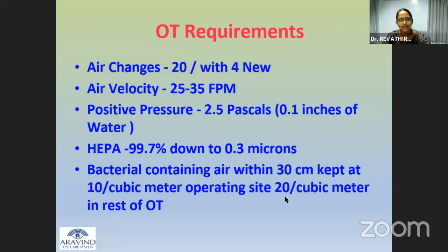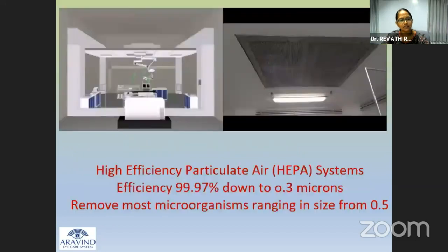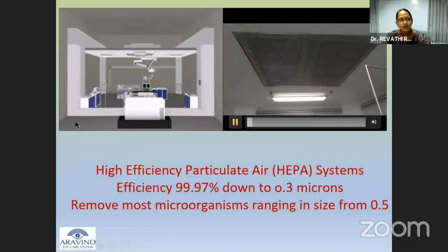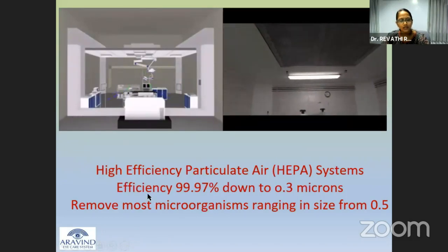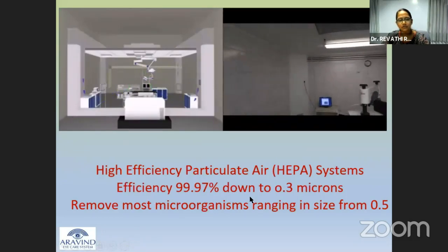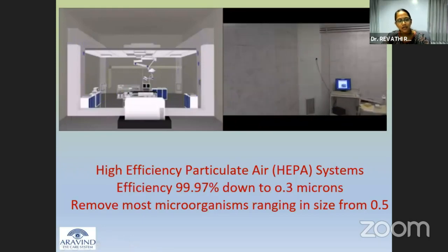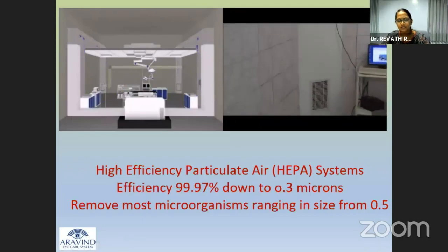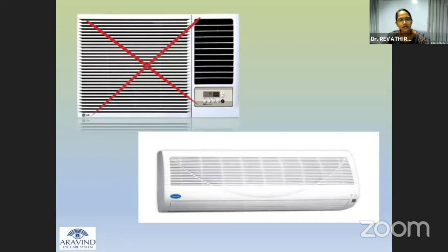So the bacteria-containing air within 30 centimeters should be kept at 10 per cubic meter at the operating site and 20 per cubic meter in the rest of the OTs. So this video gives an animated image of the high efficiency particulate air, how the HEPA system in an OT functions to reduce 0.3 micron particles by 99.97%. So most organisms of a size of 0.5 are removed.